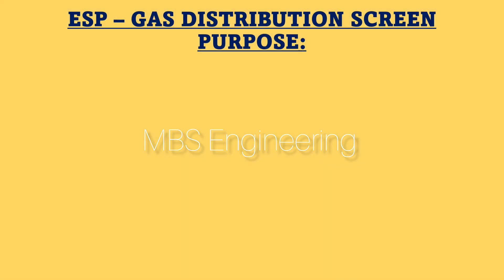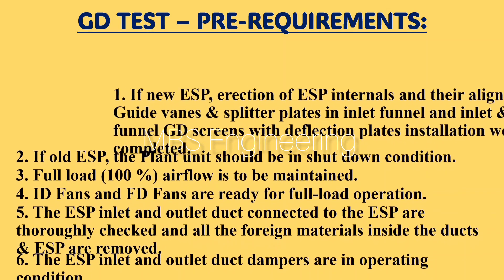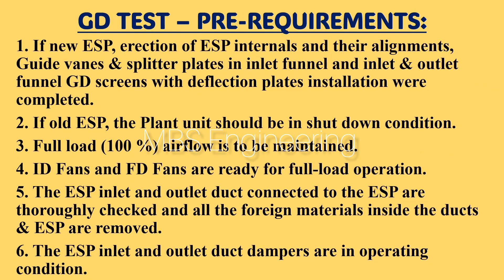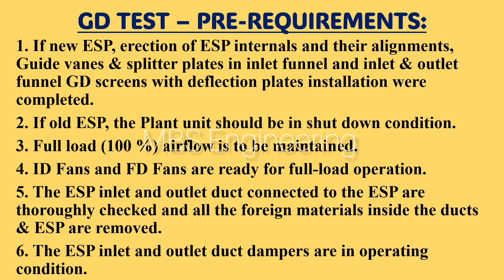Now let's discuss the pre-requirements for the gas distribution (GD) test. Point 1: for a new ESP, erection of ESP internals and their alignments — guide vanes, splitter plates in inlet funnel, and inlet and outlet funnel GD screens with deflection plates — installation must be completed. Point 2: for an old ESP, the plant unit should be in shutdown condition.